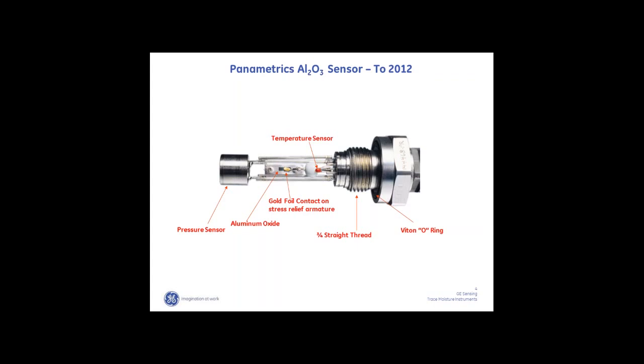This is what the sensor looks like. It has a threaded fitting — a three-quarter straight thread with an O-ring seal — that enables us to install it at pretty high pressure, up to 5,000 psig. There's also the aluminum substrate, and that black you see there is the aluminum oxide overcoated with gold. The gold is so thin that it appears black, and then there's a gold armature on top of that. This was our design up until about 2012. After 2012 we changed the design, but many people might open their probes in the field and see this sensor inside.